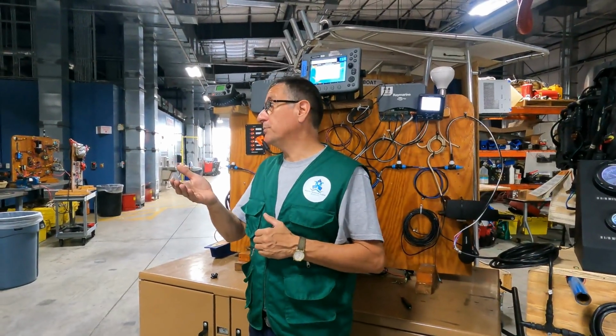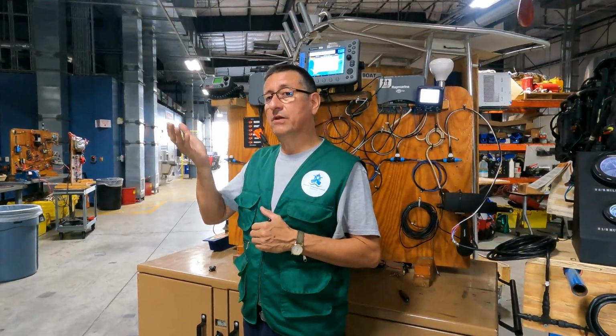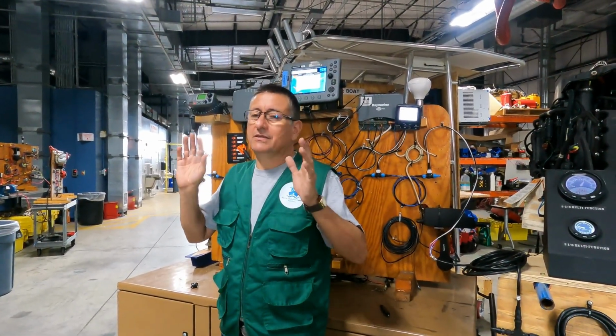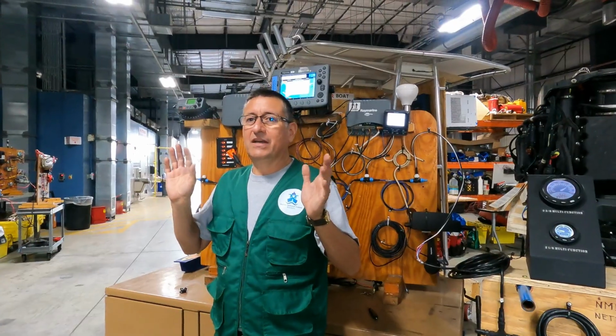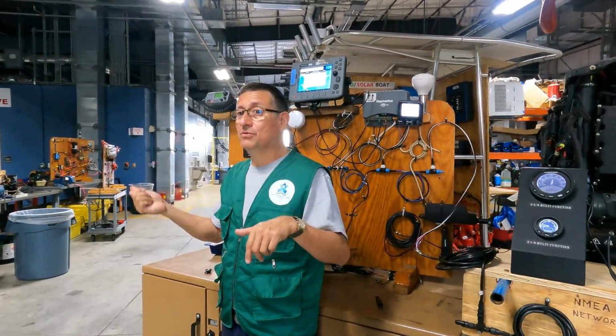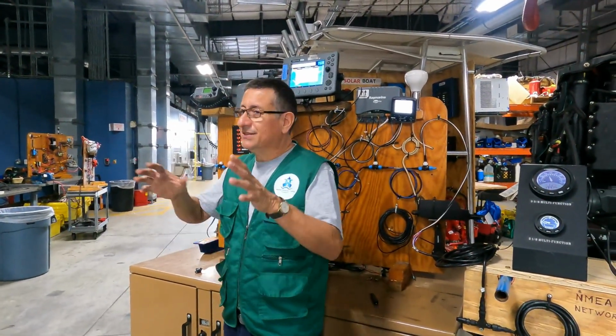I explained the troubleshooting process for high voltage, for low voltage, for high frequency. It's universal. If I have a low frequency, it's a fuel system. If I have a high frequency, it's a problem related with the governor. If I have an excessive high voltage, you need to go to the back end and check with the megohmmeter. That's the process. Doesn't matter if the generator is Kohler or Westerbeke or Onan. It's exactly the same.